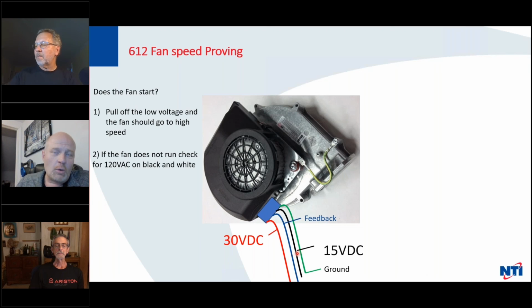And even if you knew nothing about the blower, what you should see is when you give this boiler a call for heat, you should see a change in voltage, and the blower should respond to that change in voltage. If there is no change in voltage, it means your controller didn't turn the blower on. If you do get a change in voltage and the blower does not start, it means your blower is not working, and I have seen that happen. There's an electronic failure on the circuit board that can happen where it'll run full speed, but it can't run at 50%. It has no in between. It's kind of on or off. So that is a failure that can happen with a blower. But most of the time, it's a damaged harness. So that's where I would start.